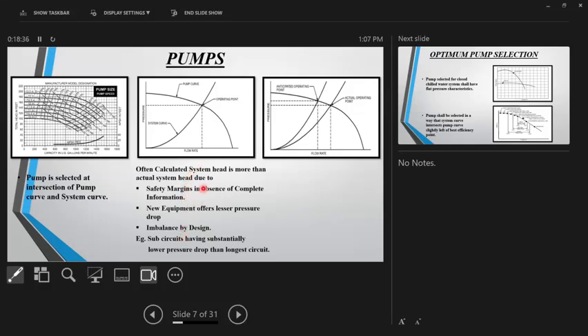There are a few variables which are actually introduced. A few of them I have tried to list. One is safety margins. When you calculate the pump head, invariably we go for some safety margins. Safety margins are not intentional, but while doing the pump head calculation, you might not have exact data of, let's say, the AHU coil pressure drop, or a strainer, or a chiller. In such cases, you would look for the submittals of similar equipment and probably take 5% extra just to be safe. Nothing wrong with that, but these things are introduced into the system. So first is safety margins.